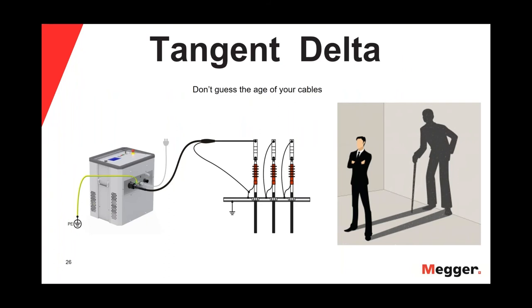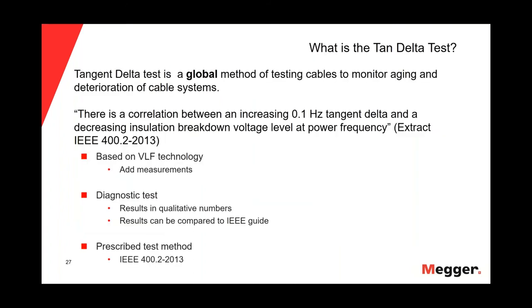We mainly use the tan delta to investigate the aging conditions of the insulation of the cable. We should not guess the age of our cables — that is what the tan delta is for. The tan delta is a global method of testing cables to monitor aging and deterioration. We know there is a correlation between an increasing 0.1 Hz tan delta and a decrease in insulation breakdown voltage at power frequency. The tan delta is based on VLF technology, is a diagnostic tool, and is prescribed by IEEE 400.2 2013.